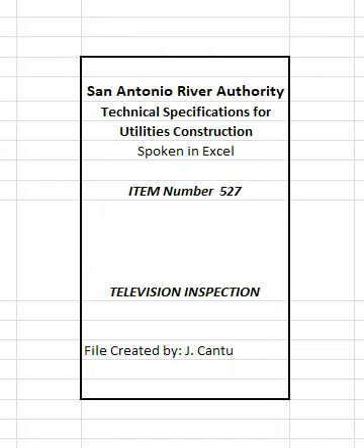Also, the flow in the section being televised shall be bypassed if the line is in service and the flow exceeds 25% of the internal pipe diameter. When the depth of flow at the upstream manhole of the manhole section being worked is above the maximum allowable for television inspection, the flow shall be reduced to allowable levels by temporarily plugging or blocking the flow or bypass pumping, as approved by SARA. The contractor shall not be allowed to float the camera.